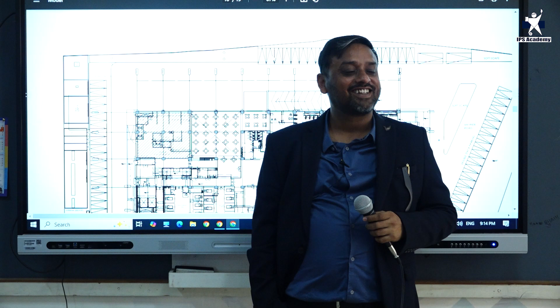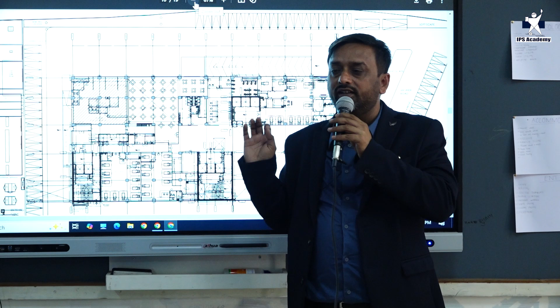So what about the UPS system? Very nice. So UPS system is dedicated for multiple areas. I actually remembered that point to discuss, but I forgot. Coming to the OTs, they have a different UPS system from the building. OTs have a different surgeon control panel from the other buildings. OT has a different anti-static flooring, because during the operation the doctor can't take the risk. So the UPS is separate, the lighting control panel, the surgeon control panel is separate. So the UPS dedicated to OTs are different.